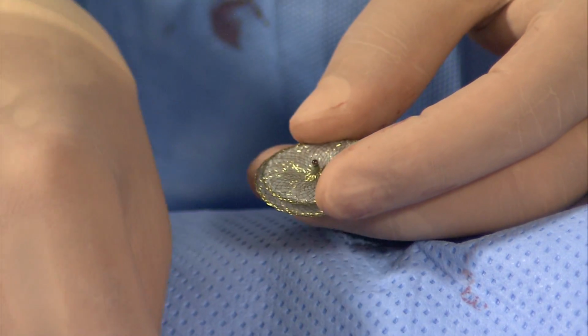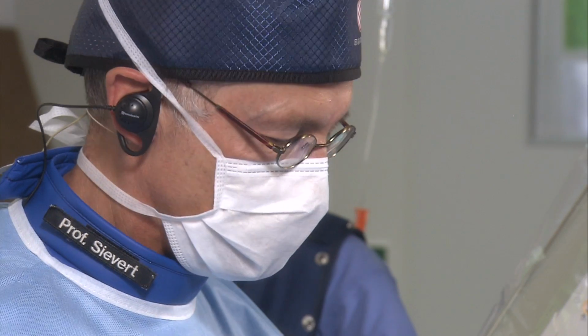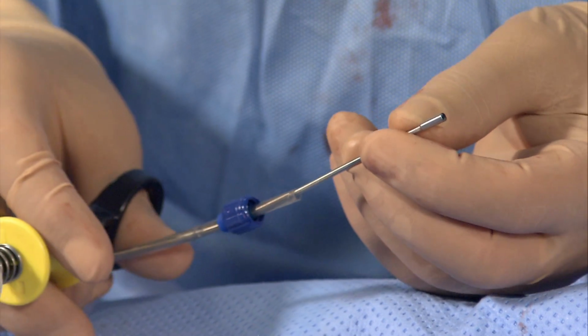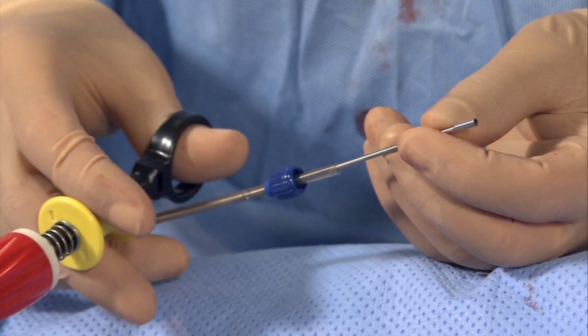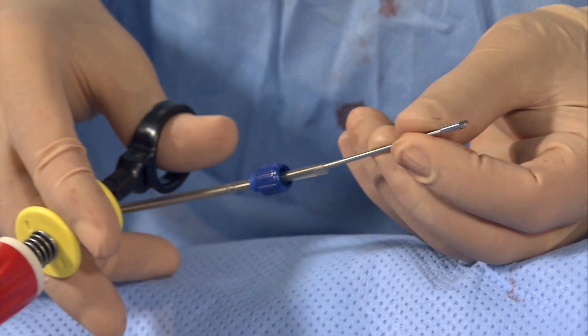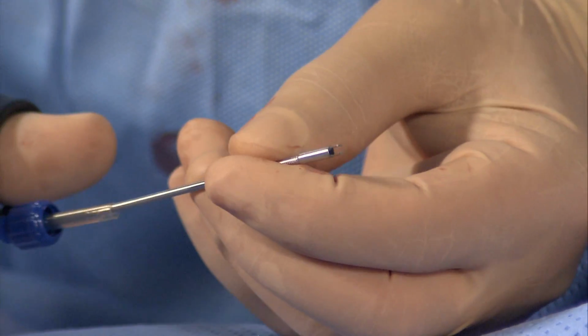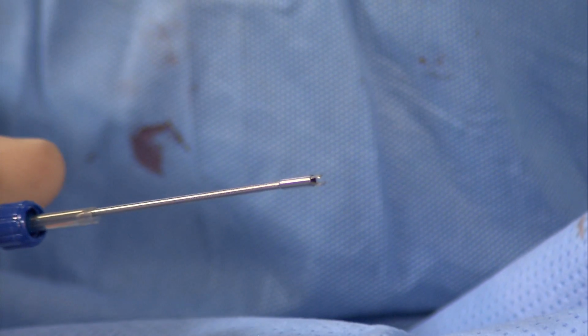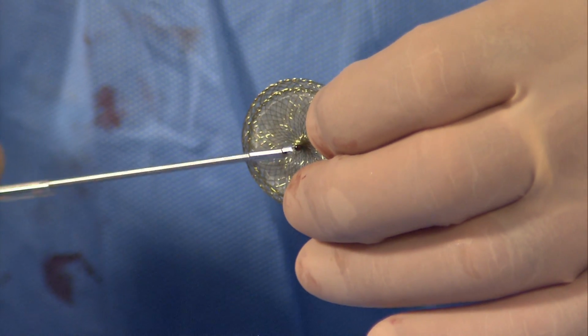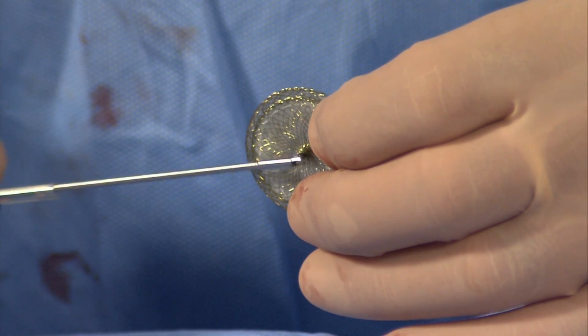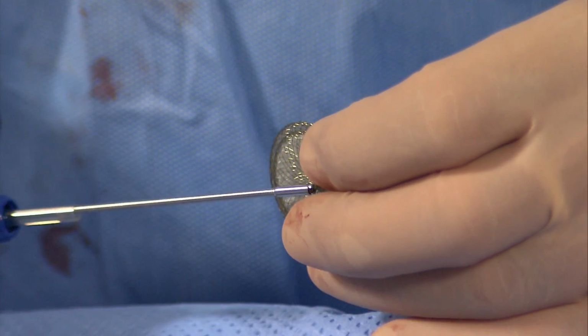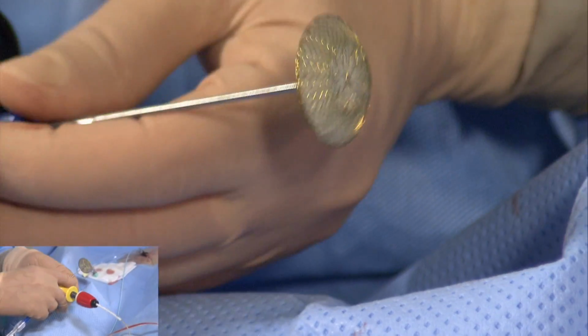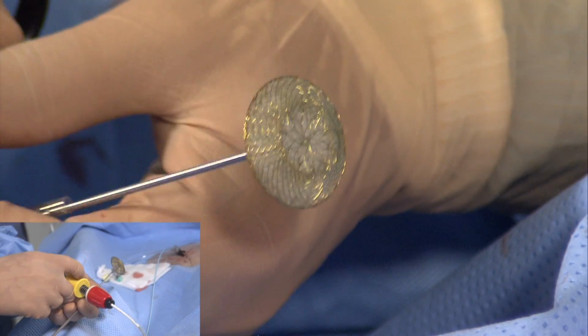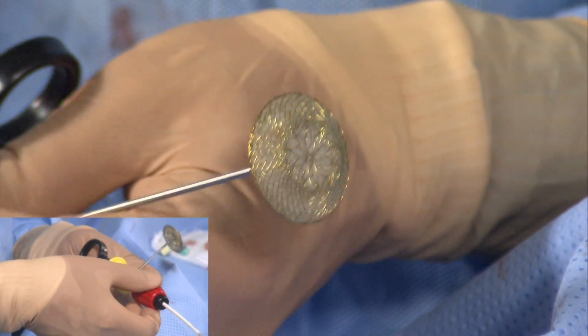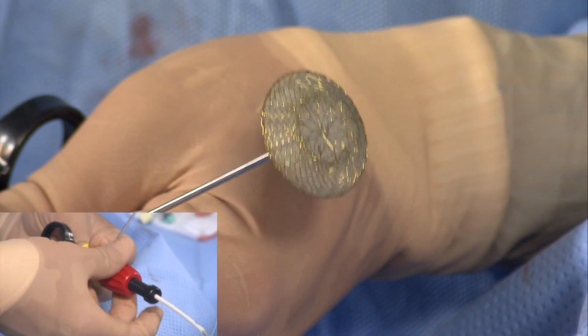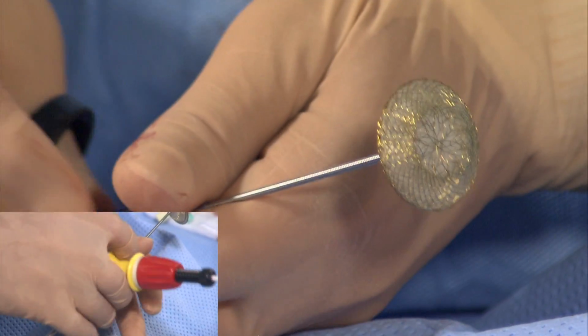So how can this be fixed to the delivery system? The delivery system has a little capsule at the distal end, and when I pull or push this knob here, then you can see that a little, let's say, clamp with two arms comes out, and I will push this ball of the device into this clamp. And then release the hub, and then it is fixed. And in order to prevent dislodgement of the device before I want to have it dislodged, I screw it on here. So now the connection between the device and the delivery cable is fixed.